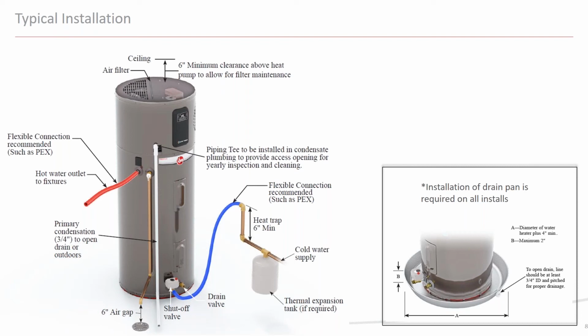I will say for the efficiency, yeah, there is a drop of efficiency at 37 degrees. Our efficiency is still at about 300% or a 3 UEF for the heat pump. In the summertime, when it's hot, if you have a garage that's about 100 degrees, I think Sacramento just had a study in a garage where they were getting 6 COP or 600% efficiency in the summertime for their heat pump water heater. So there is a difference. It is still very efficient, especially considering electric resistance is only about 100% efficient when running. So don't be scared about putting these in a garage when it gets cold in the wintertime.